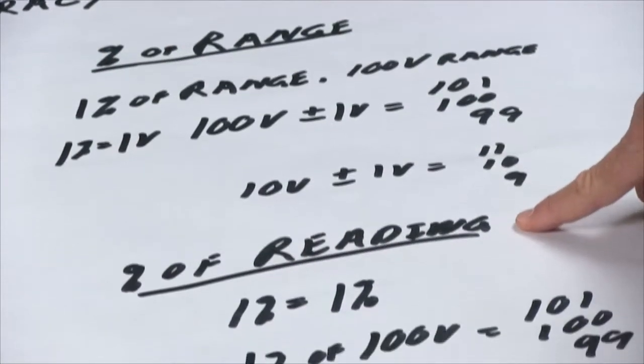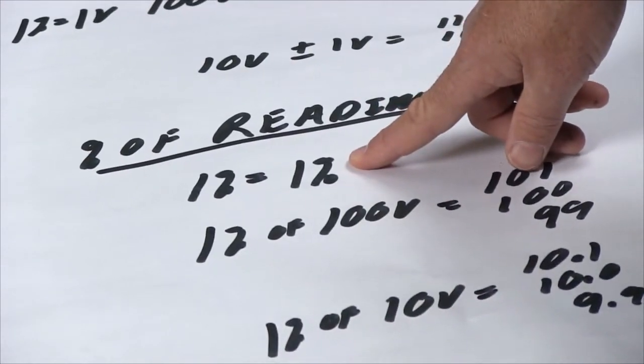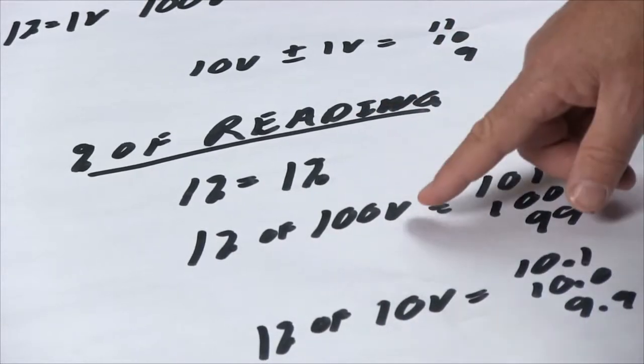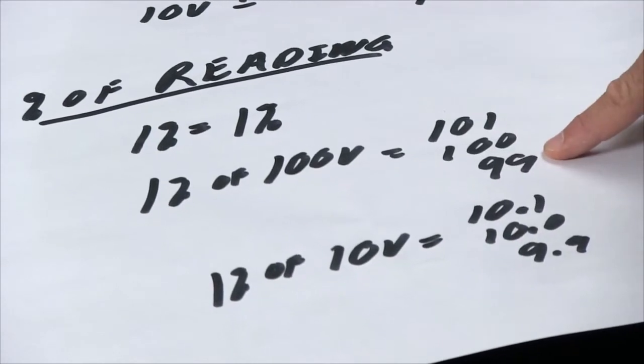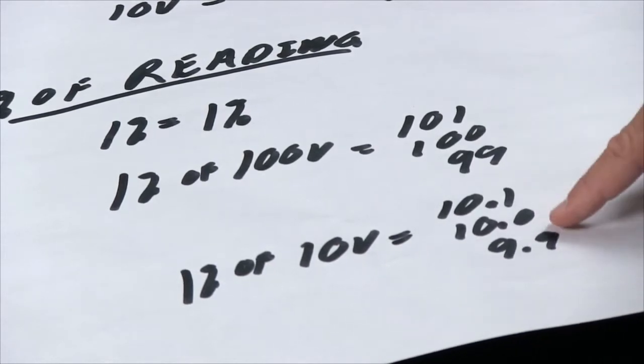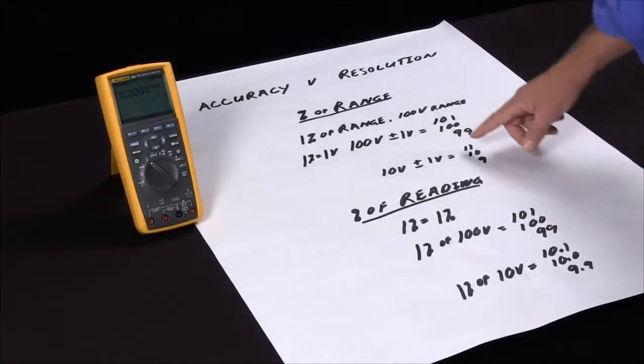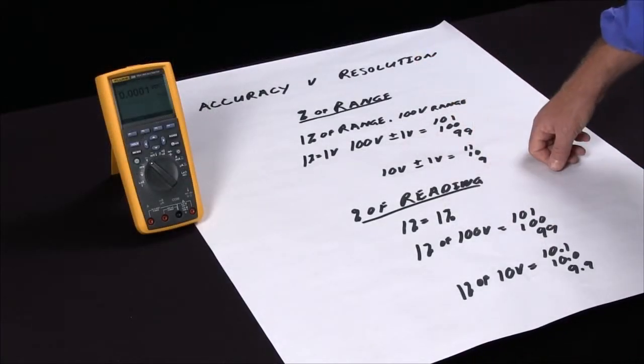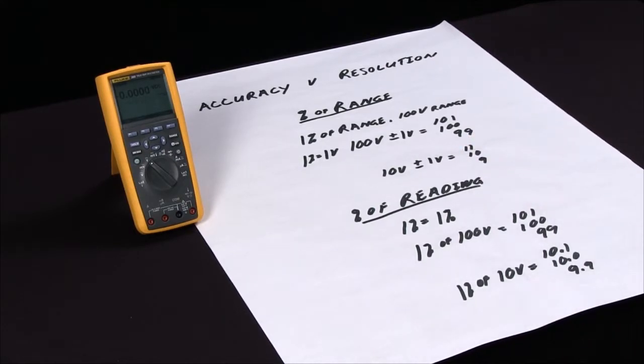A better way is to buy an instrument that has percent of reading, and then one percent is one percent. It doesn't matter what value or what range you're on. So here, one percent of a hundred volts is still that plus or minus one volt. One percent of ten volts is plus or minus a tenth of a volt. So here with percent of reading, the accuracy is a tenth of a volt. The same thing specified with percent of range, one percent is now plus or minus one volt. So it's very important if you're looking for accurate readings to make sure you select the device with a percent of reading versus a percent of range.